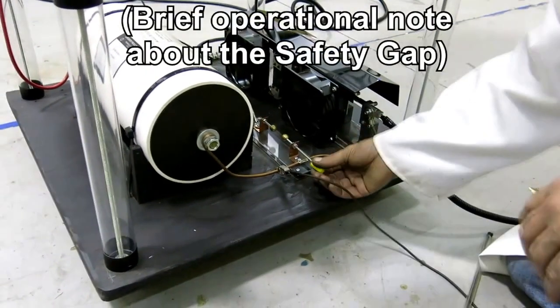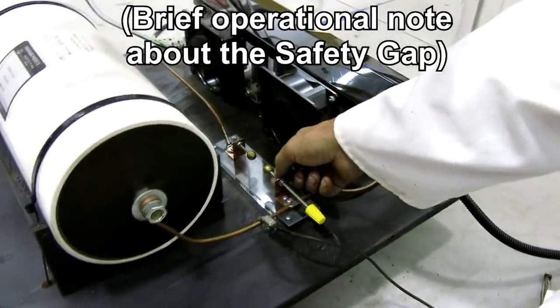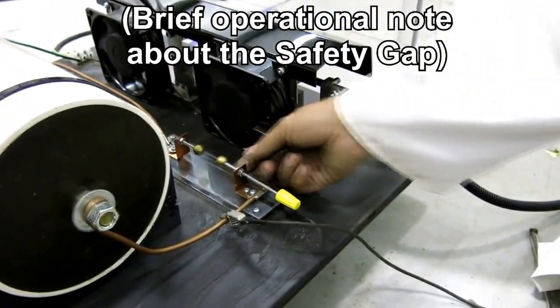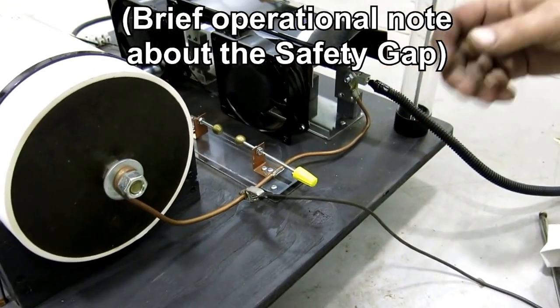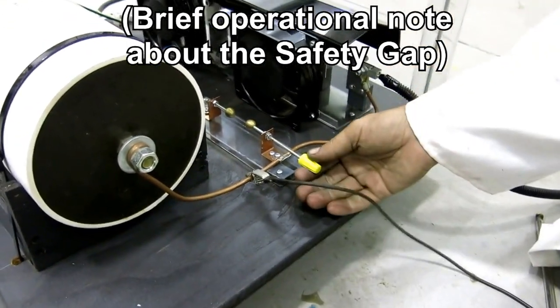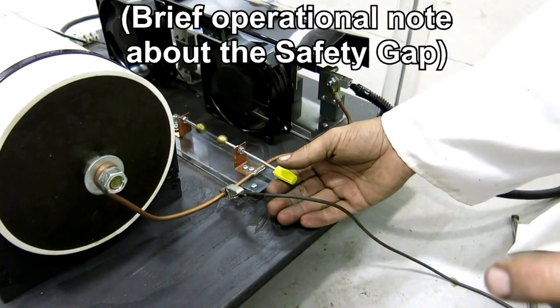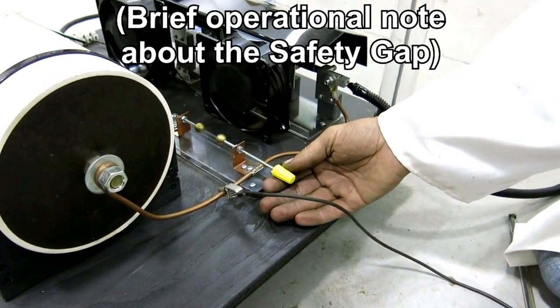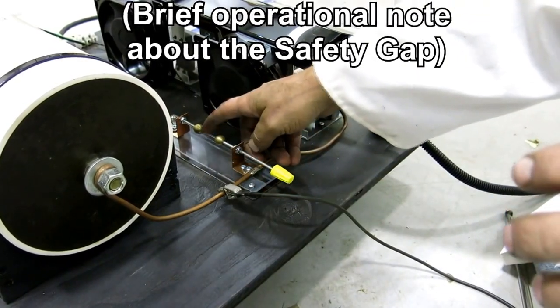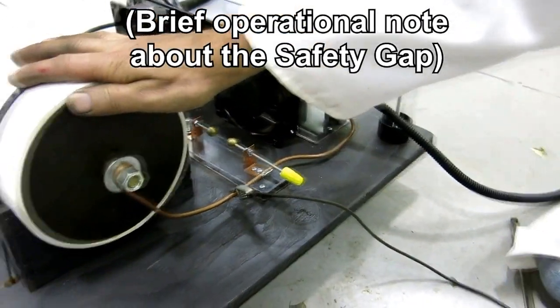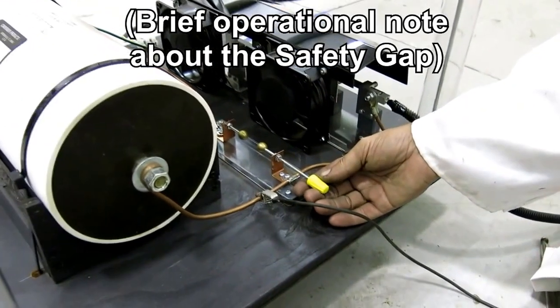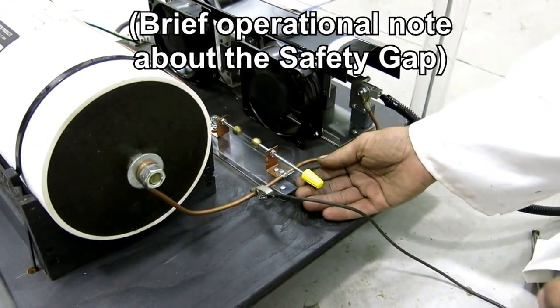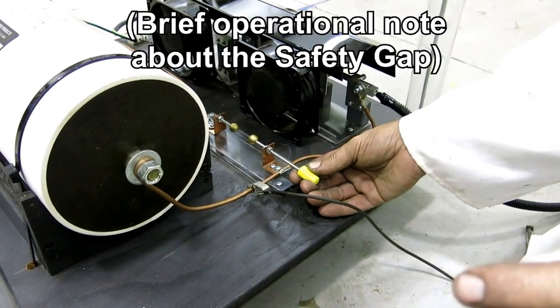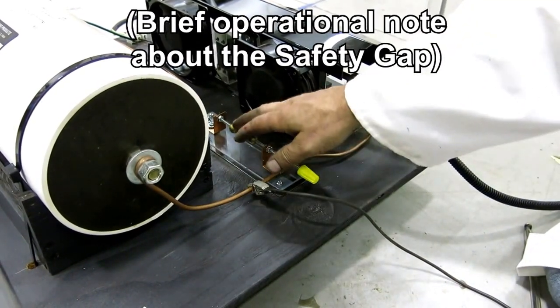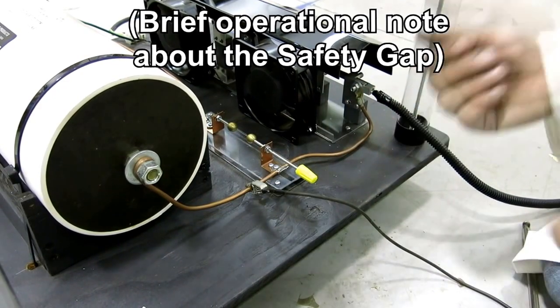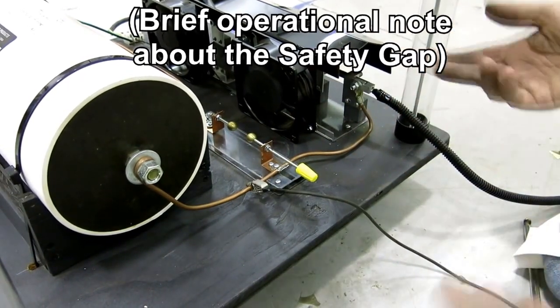Now the safety gap right here, it's part of the operation, but we're here anyways, is set for over voltage. If you're using the unit and you hear this loud pop, pop, it's the safety gap. It's nothing major, but if you do hear some pops, this one is set just on the fringe of the voltage that's going to it. If you do get a pop once in a while, you can back this off about a quarter turn at a time until the popping just stops. You don't want to back it off too far, where this gap is important, in case there's any breakdown, it'll jump that and not destroy everything else.